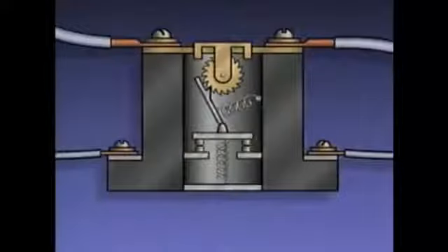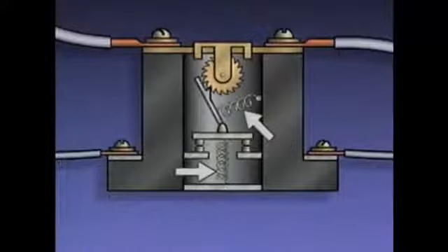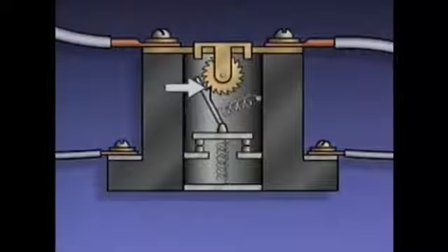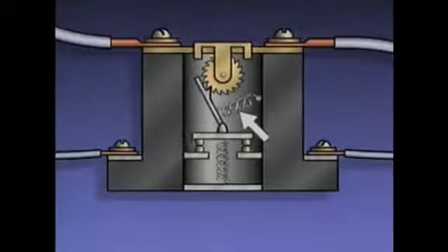Now let's look at the entire solder pot. From this angle, we can see the top of the ratchet wheel here. We can also see that the solder pot has a mechanical linkage, movable contacts, which are in the motor controller's control circuit, and 2 springs. The ratchet wheel, which is set on the rod, holds the mechanical linkage in place. The movable contacts are attached to the mechanical linkage, and the stationary contacts are positioned in the casing of the overload device. The linkage spring holds the mechanical linkage against the ratchet wheel, and the contact spring pushes against the movable contacts.